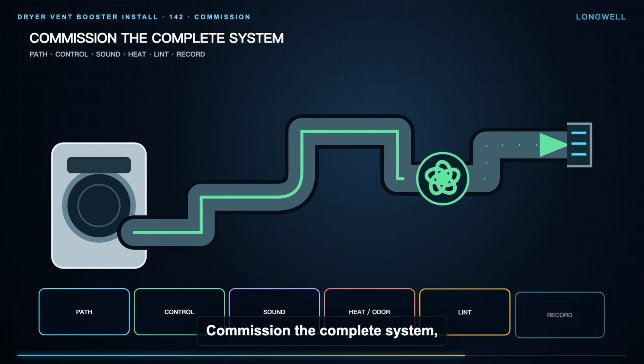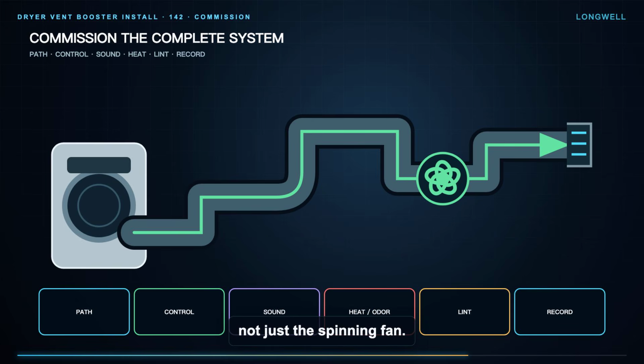Commission the complete system, not just the spinning fan. Re-inspect the entire exhaust path and outdoor termination. Verify that the control sequence follows the exact instructions, the ventilator responds through the intended dryer cycle, and the system returns to its required state afterward. Check for abnormal sound, vibration, heat, odor, lint escape, loose joints, control faults, or a termination that does not behave normally. Record the model, documents, installation location, control check, and maintenance access without inventing performance numbers.